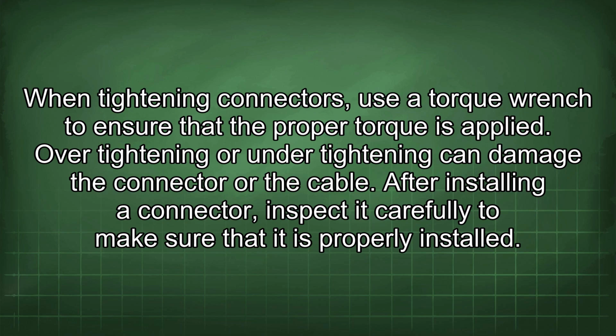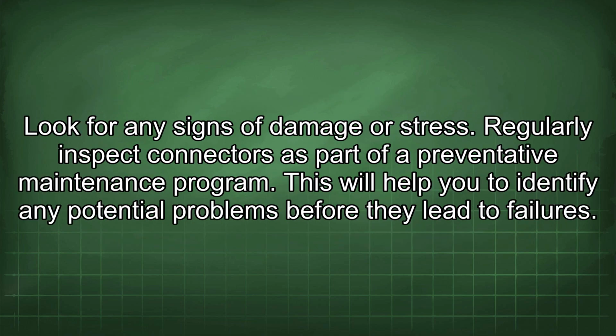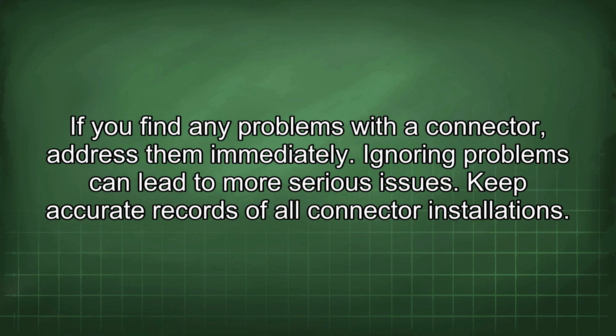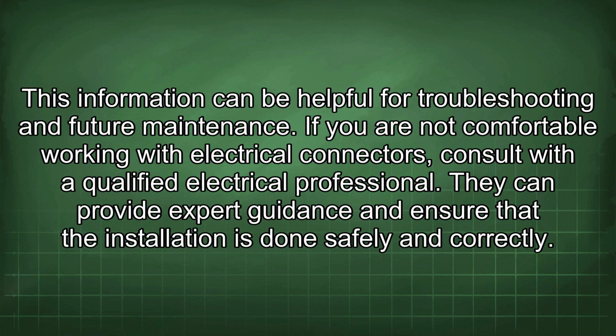After installing a connector, inspect it carefully to make sure that it is properly installed. Look for any signs of damage or stress. Regularly inspect connectors as part of a preventative maintenance program. This will help you to identify any potential problems before they lead to failures. If you find any problems with the connector, address them immediately. Ignoring problems can lead to more serious issues. Keep accurate records of all connector installations. This information can be helpful for troubleshooting and future maintenance.